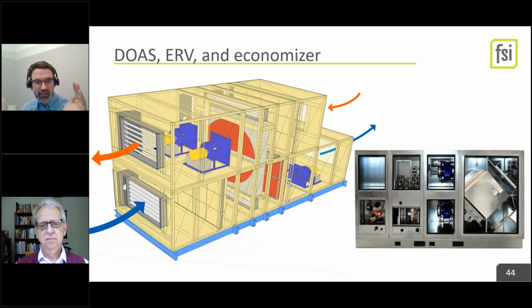That's very confusing, and you need pretty advanced controls. You need temperature and humidity on outside air, supply air, and return air, the exhaust airstream, to know if it's a good idea to turn on your economizer at any given point. At least in the enthalpy wheel, the energy recovery version. In heat recovery, you can do it on temperature alone because it's sensible alone. Let's go to the next slide.